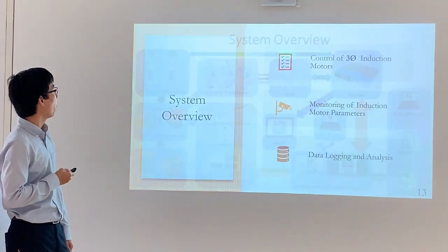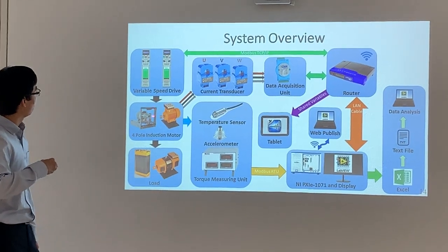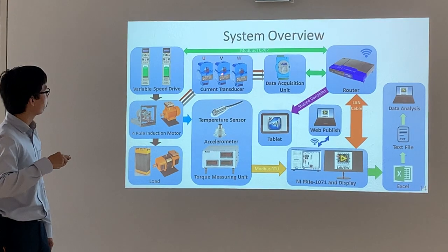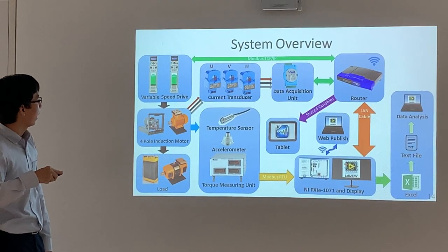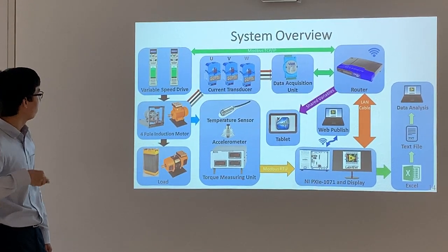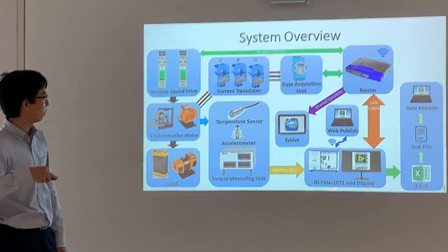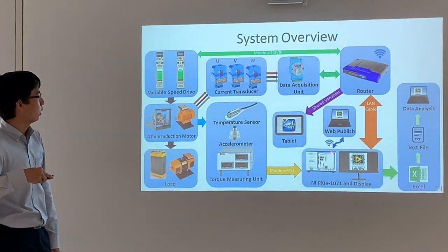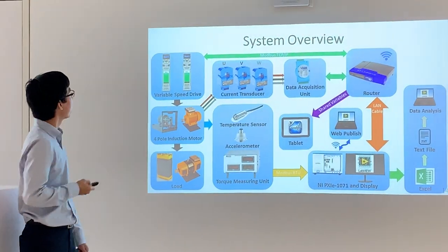I will be talking about the system overview. We have the VSD driving the induction motor. The parameters are monitored by the current transducer, temperature sensor, and accelerometer. The current transducer is linked to the DAQ, then linked via Modbus TCP/IP to the router, same for the VSD. The temperature sensor and accelerometer are linked via Modbus RTU to the NI PC. We have shared variables for tablet viewing and web publishing, and data analysis which Lina will go through later.